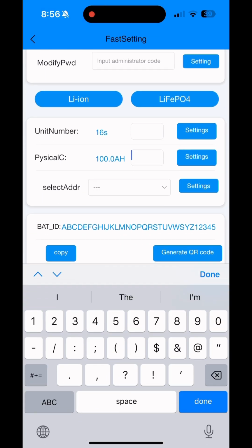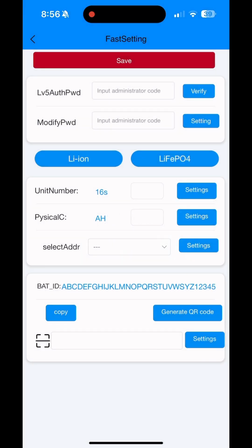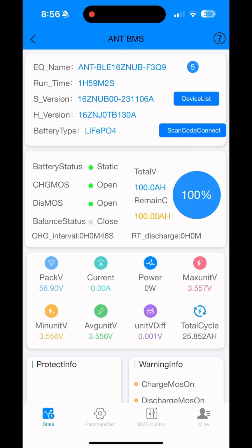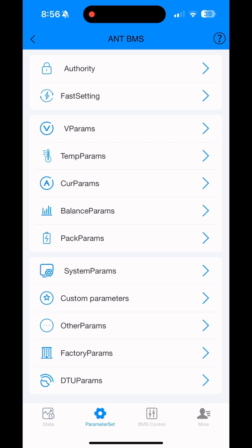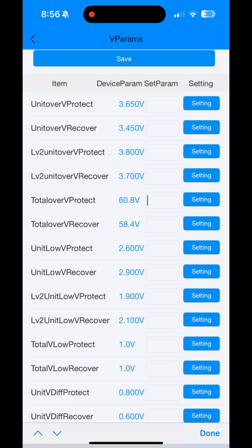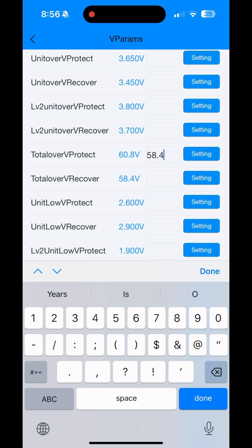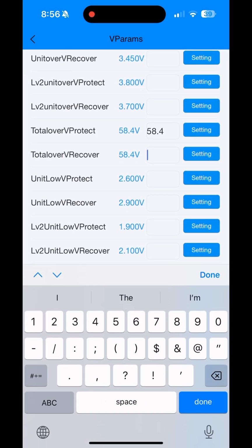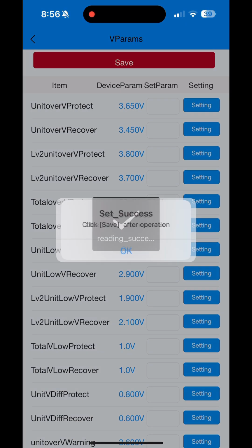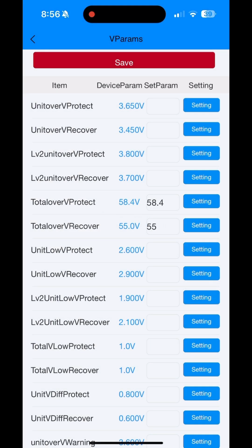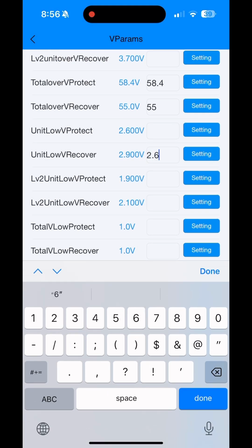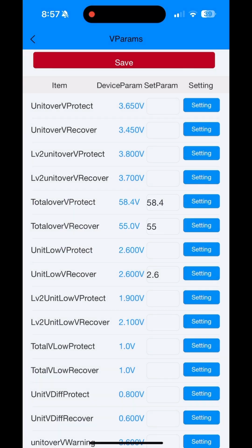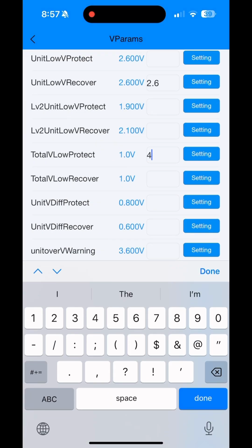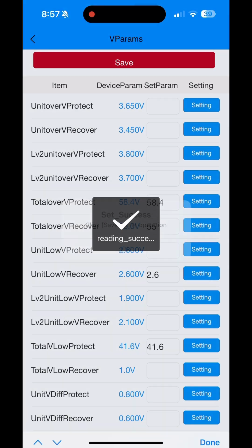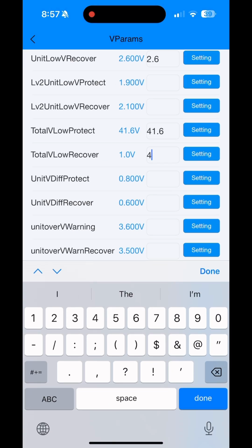You'll set it to LiFePO4, 16 cell, and 100 amp hours. Next, go to the voltage parameters and change total voltage protect to 58.4, total recover to 55. We'll change the low voltage protect to 2.6, the low voltage protect for the pack to 41.6, and the recover to 41.6.